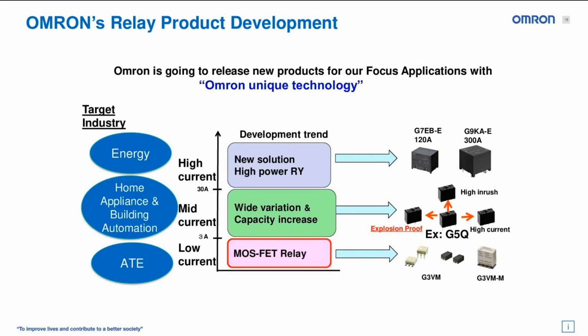So solar power inverters, energy storage, uninterruptible power supplies, EV charging. These are all very high current, high voltage applications. And we're looking to displace contactors with very high level PCB relays that bring everything board-based and don't rely on manual assembly of contactors. So that's with our release of G7EB-E, 120 amps, 800 VAC, and the highest PCB power relay on the market today, which is the G9KAE, which is 300 amps at 1000 volts AC.